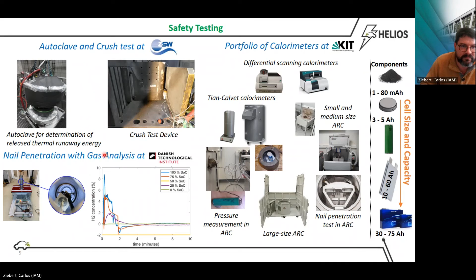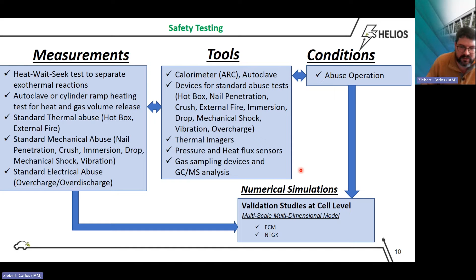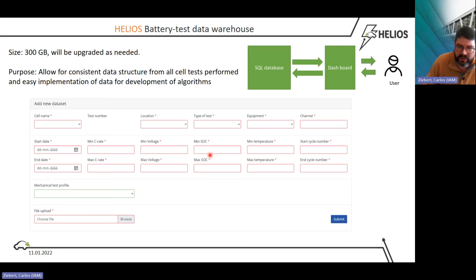So for the safety testing, I have basically shown the main things already. We have the heat wait seek test in the accelerating rate calorimeter. We have the autoclave. We can do the standard thermal abuse, mechanical abuse and electrical abuse. This also goes into a simulation of the thermal propagation modeling. Then we have the battery test database, a data warehouse where all the different data of the different testing partners are stored. This is just an overview of how it looks. If you add a new data set, you put in the type of test and which equipment you used, so that all metadata are available later. This can then be used by those developing the digital twin to put everything together.